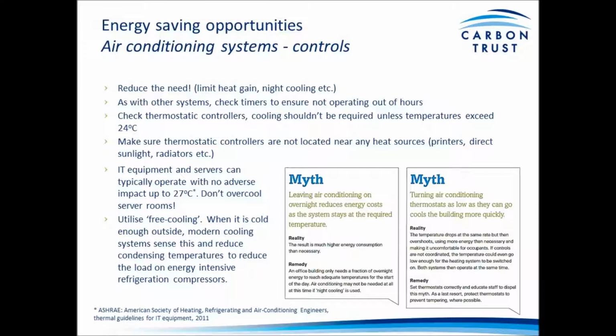Another common myth is that you turn down the thermostats as low as they can go so it cools the building more quickly. This is not true again. The building will cool at the same rate. It will just overshoot that final temperature and overcool the building. And again, both energy management and staff engagement are needed to really implement these effectively. But certainly, set your building to the correct temperature and run your air conditioning systems for the hours you're in the building, not any longer.